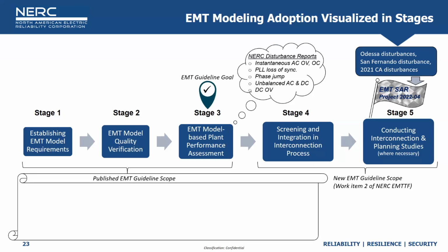Our goal, having gone through the first three stages, is to cover most of the risks that we've been identifying in the disturbance reports, such as instantaneous trippings, PLL loss of synchronism, phase jump, unbalance, AC/DC protection tripping, and DC overvoltage tripping. Most of these could be caught in the stage three assessment.